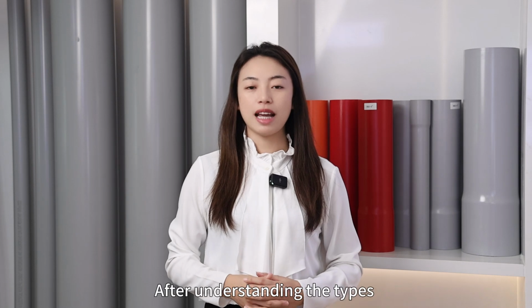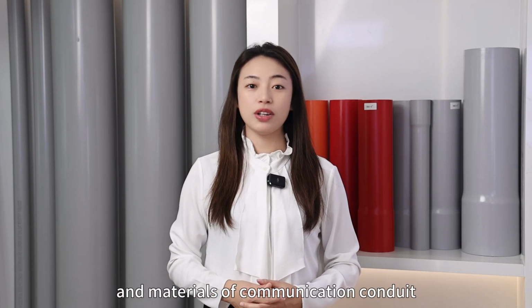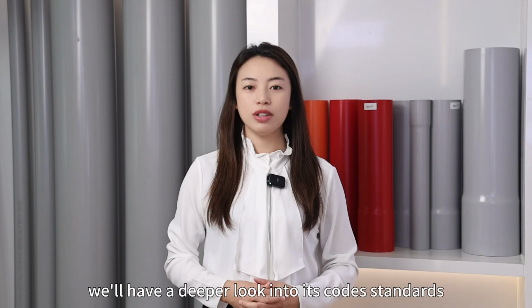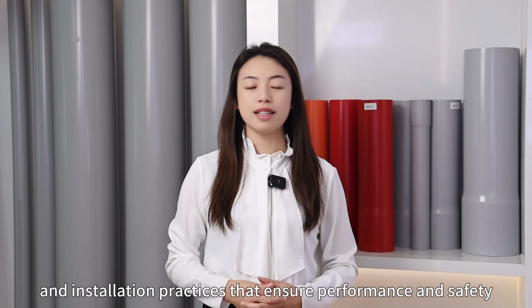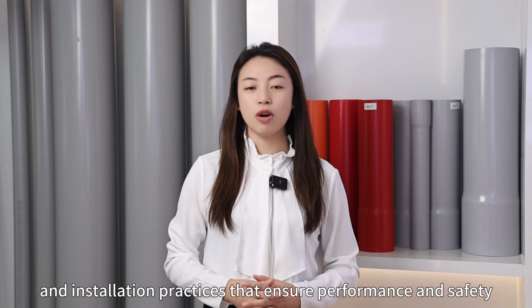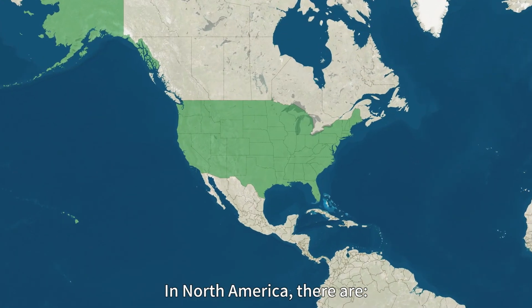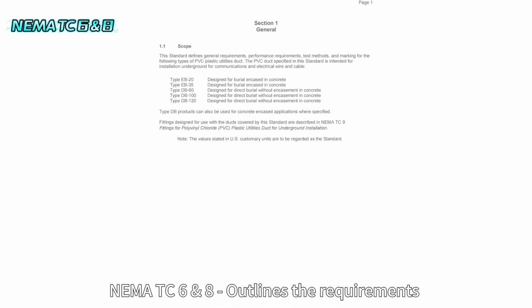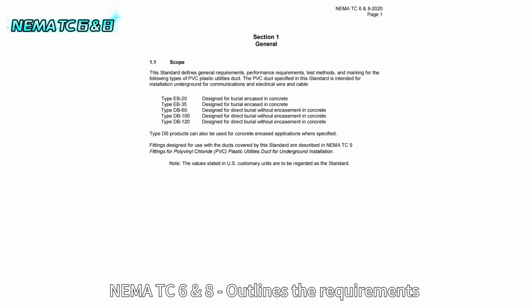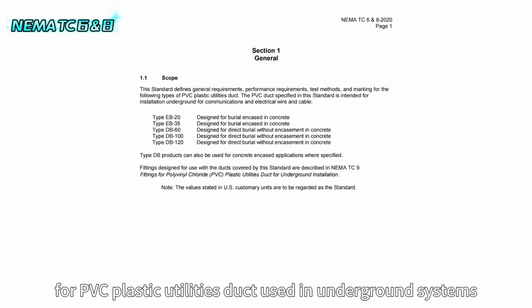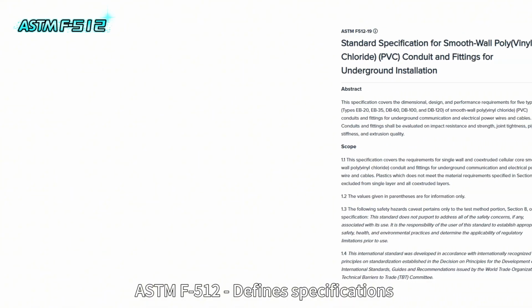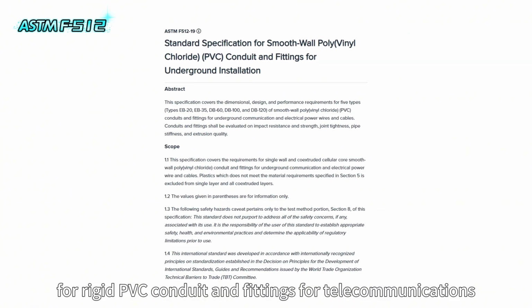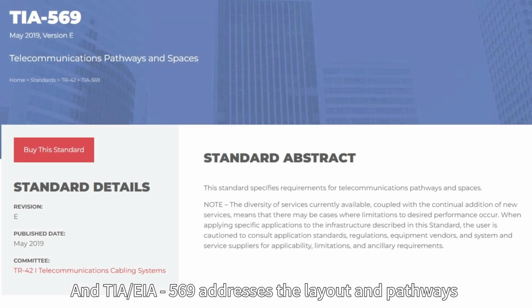After understanding the types and materials of communication conduits, this video will have a deeper look into its codes, standards, and installation practices that ensure performance and safety. In North America, NEMA TC 6 and 8 outlines the requirements for PVC plastic utility ducts used in underground systems.